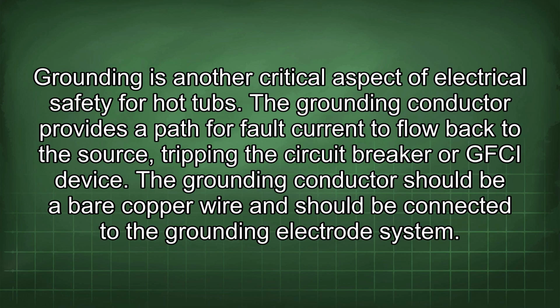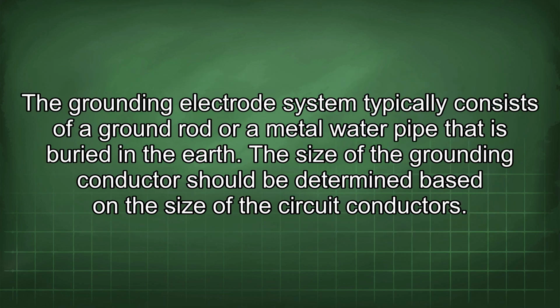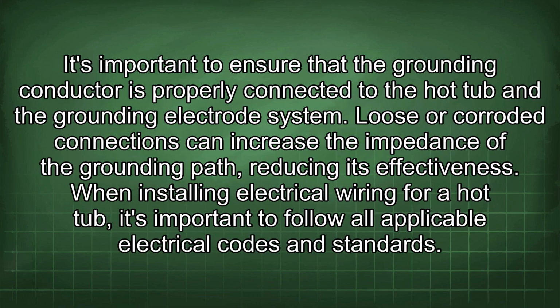Grounding is another critical aspect of electrical safety for hot tubs. The grounding conductor provides a path for fault current to flow back to the source, tripping the circuit breaker or GFCI device. The grounding conductor should be a bare copper wire and should be connected to the grounding electrode system. The grounding electrode system typically consists of a ground rod or a metal water pipe that is buried in the earth. The size of the grounding conductor should be determined based on the size of the circuit conductors. It's important to ensure that the grounding conductor is properly connected to the hot tub and the grounding electrode system. Loose or corroded connections can increase the impedance of the grounding path, reducing its effectiveness.